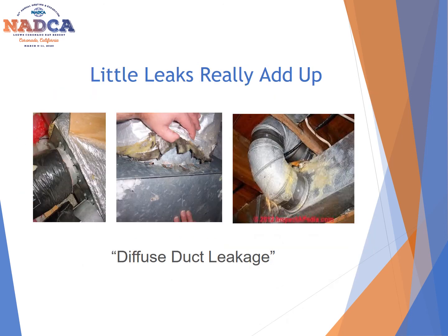Often it's not just one big duct issue that you have where it's leaking all your air. Often it's a bunch of little tiny things that are all over the place. You look at the picture on the left right here, you can see the connection box from the plenum to the ductwork itself. It's not sealed. And the same thing with the picture in the middle. All that air is able to escape, and you have a bunch of little pockets of air that are escaping, which creates all kinds of issues.